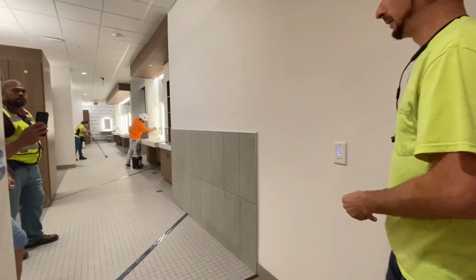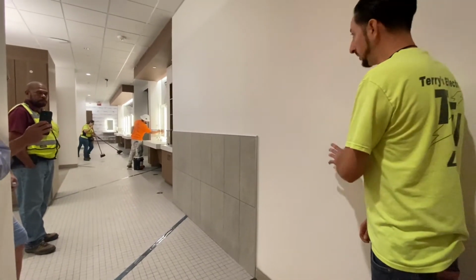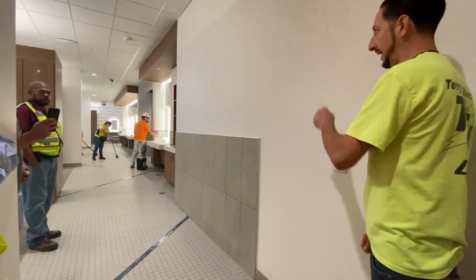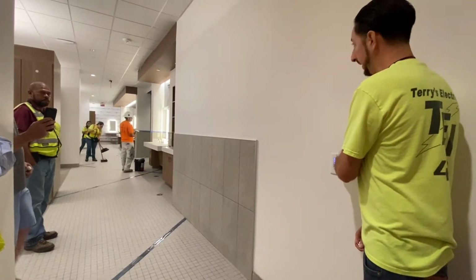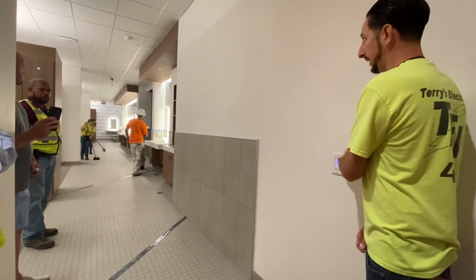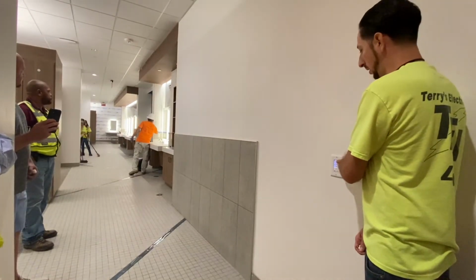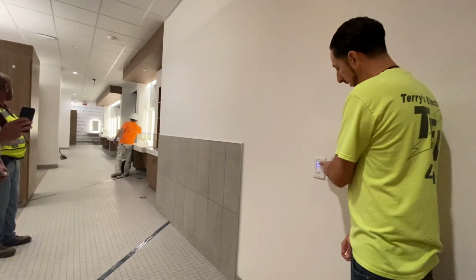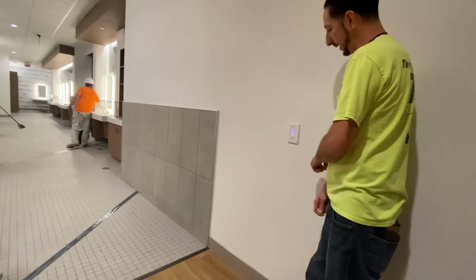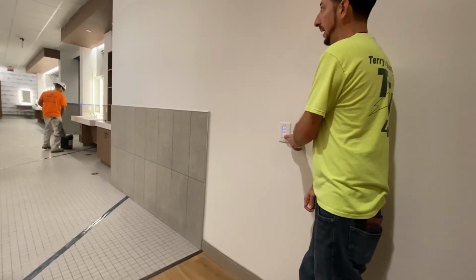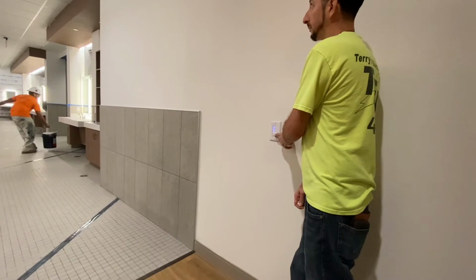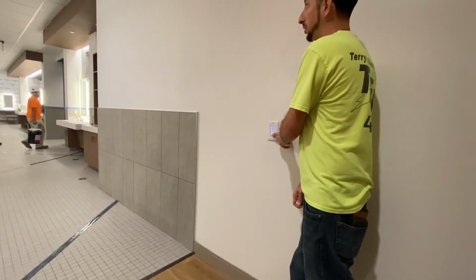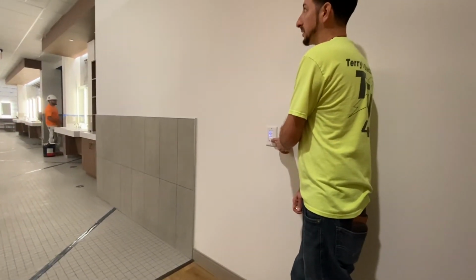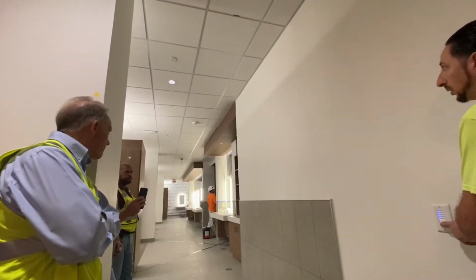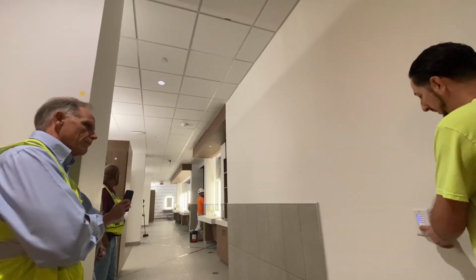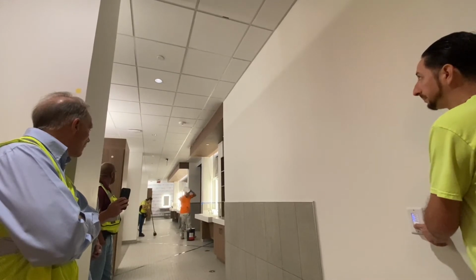And the arrows? There's only one dimmable load in here, which is the can lighting. The can lighting is on zone 1, so we'll make sure that's 1 and turn that back on. If you want to dim the cans, you hold zone 1, it'll blink, and then you can ramp down that load. It takes a second for the signal to get to the processor, so you have to be patient with it, and then you can ramp that back up.